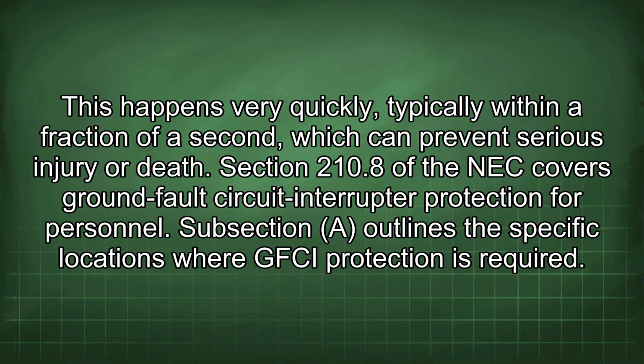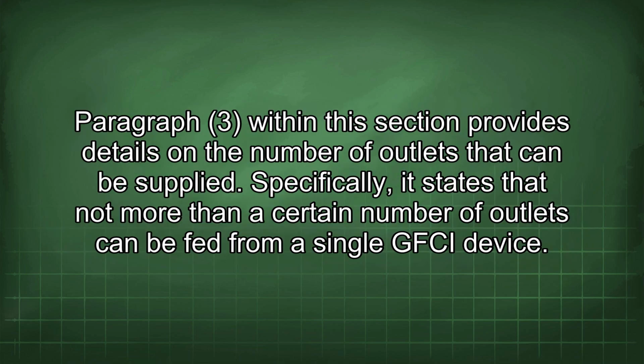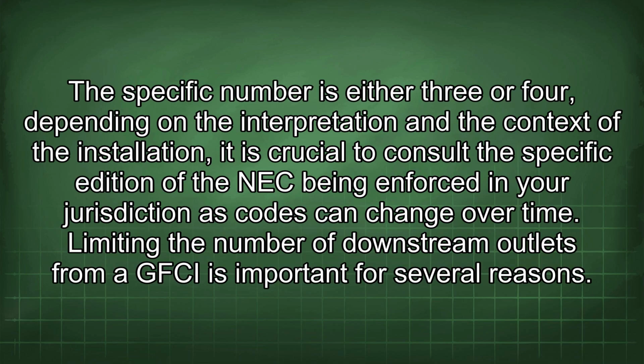Section 210.8 of the NEC covers ground fault circuit interrupter protection for personnel. Subsection outlines specific locations where GFCI protection is required. Paragraph 3 within this section provides details on the number of outlets that can be supplied. Specifically, it states that not more than a certain number of outlets can be fed from a single GFCI device. The specific number is either 3 or 4. Depending on the interpretation and the context of the installation, it is crucial to consult the specific edition of the NEC being enforced in your jurisdiction, as codes can change over time.